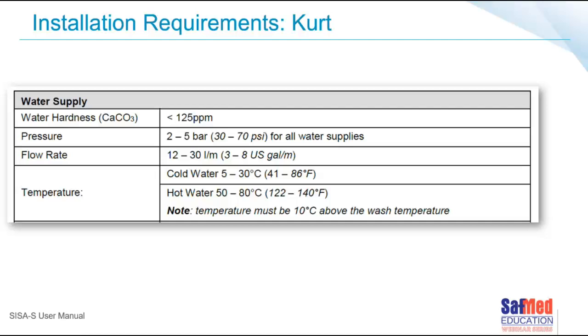It needs a good water quality. Hard water can affect the cleaning of the instruments. It can also create unnecessary breakdowns of the ultrasonic cleaner over time because of buildup of calcium in the water supply. The water pressure is very important. It needs to have the right water pressure for inlet water. So for hot or cold water, follow the instructions for use from the manufacturer, and they'll state what the water pressure should be.